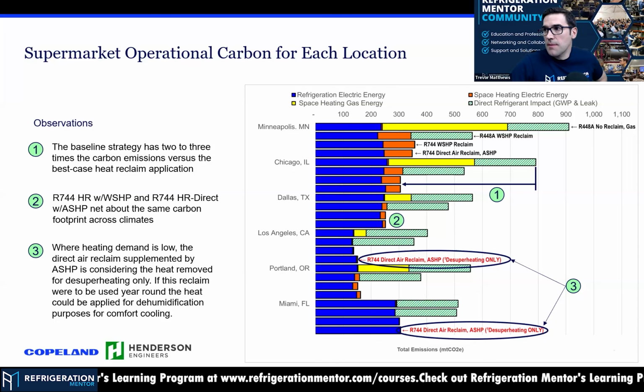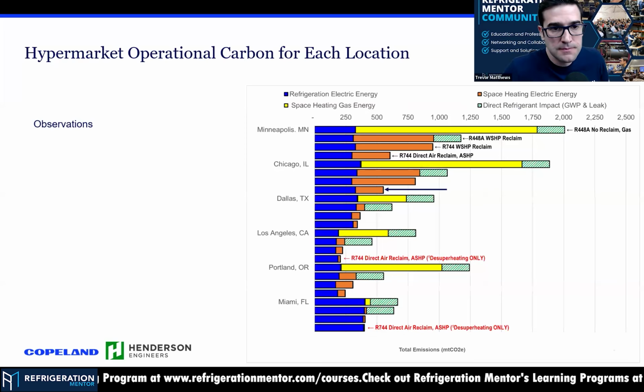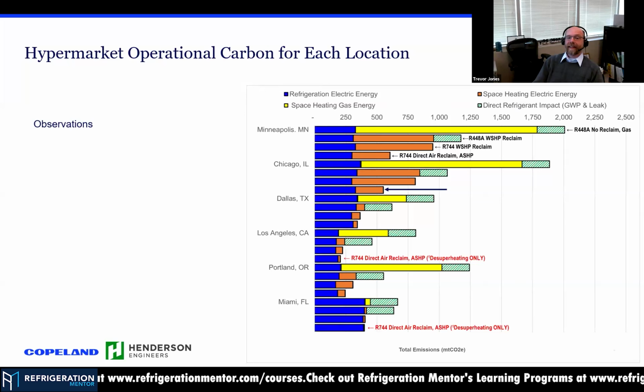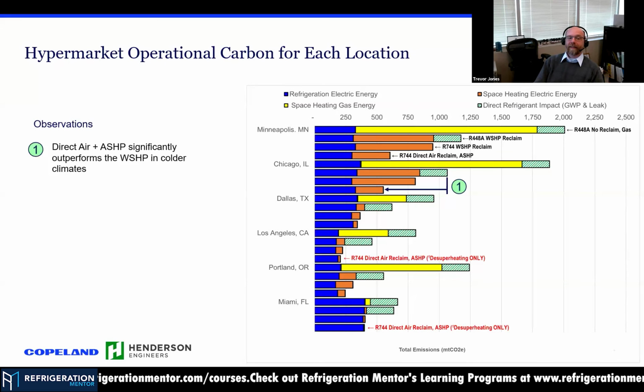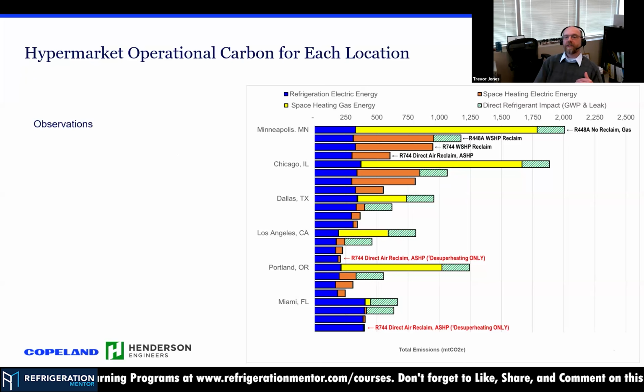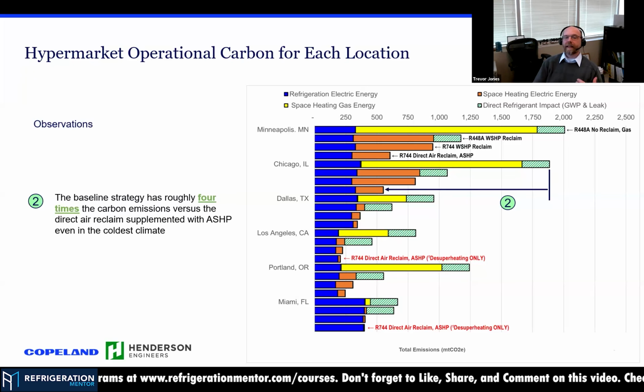Okay, let's check out the hypermarket, that would be the next one, right? Yeah, and again here it's a little bit different because the water source heat pump needs so much additional heating energy inputted that the air source heat pump, especially in the colder climates, really shines. In the milder climates they're a lot closer. When you look at Dallas and Portland, the water source heat pump seems to make up ground, but the air source is still so much better.